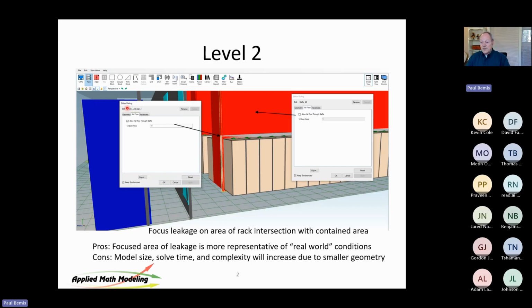And I've put a baffle. Now in CoolSim, a baffle, we have a system priority hierarchy. So the second one has been added to the system. It's most recent. Whatever object is put in the model most recently has priority. So these are coplanar, but this one has priority, this leakage, because it was put in there second, put in there sort of last.